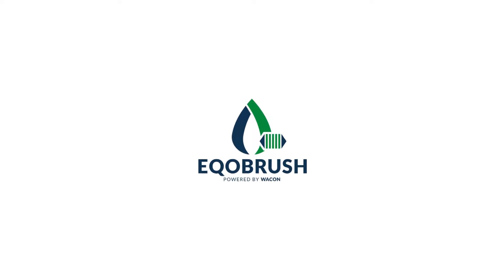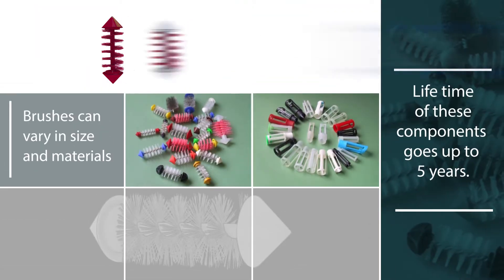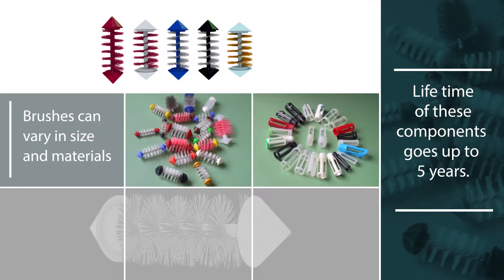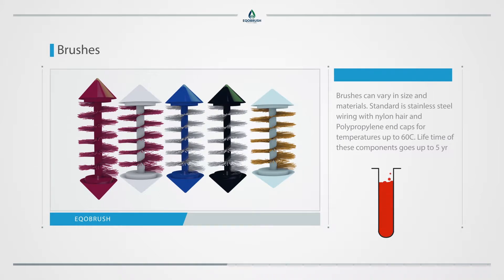The EQOBRUSH system components include brushes with catch baskets. Brushes can vary in size and materials. Standard is stainless steel wiring with nylon hair and polypropylene end caps for temperatures up to 60 degrees Celsius. Lifetime of these components goes up to 5 years.